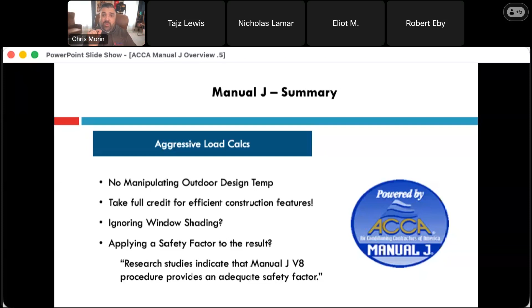Make sure you don't apply any of your own safety factors already, because the process allows for slightly oversizing when you go to equipment selection. The software has to round all these devices as you add them in, so the decimal points will go on forever. When I was trained by Hank Rakowski years ago, he said that when they're approving software, there's already about a 20% oversizing factor built into an aggressive load calculation. So if you round up or manipulate design temperatures, you can see how this process could get really out of hand. So be aggressive—really important.